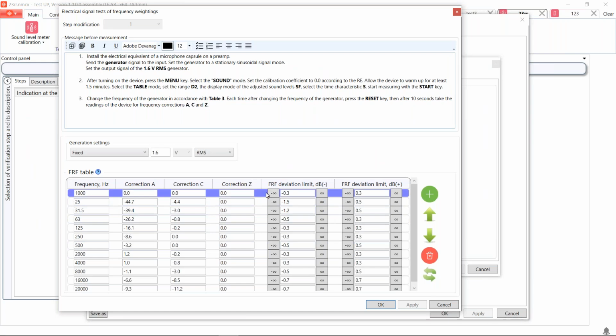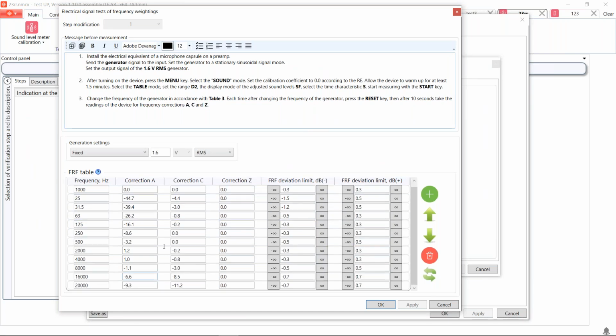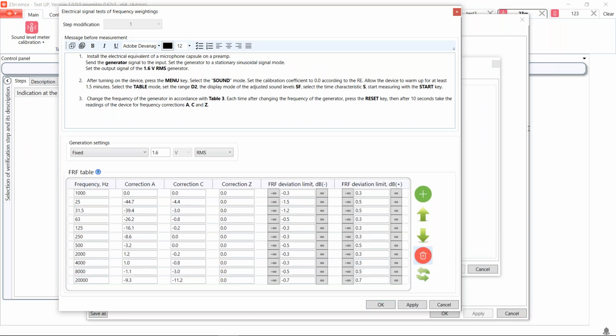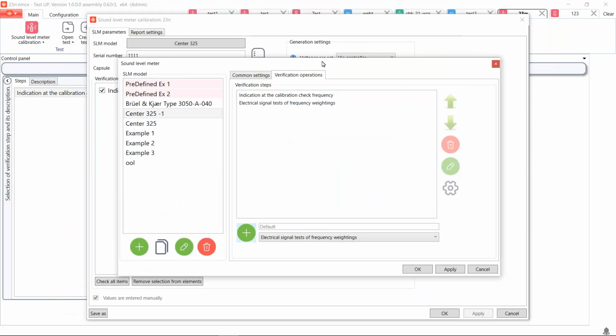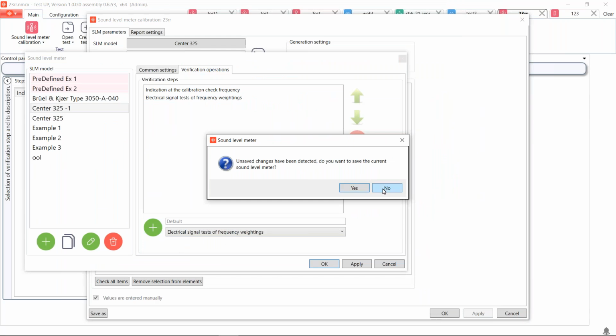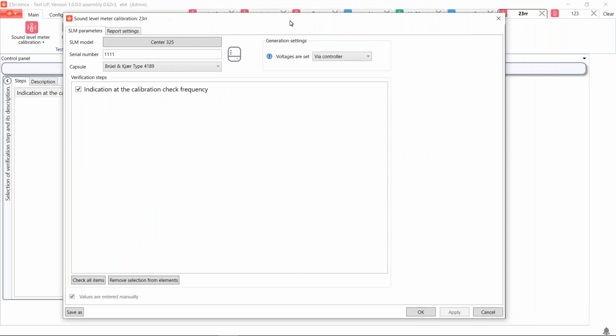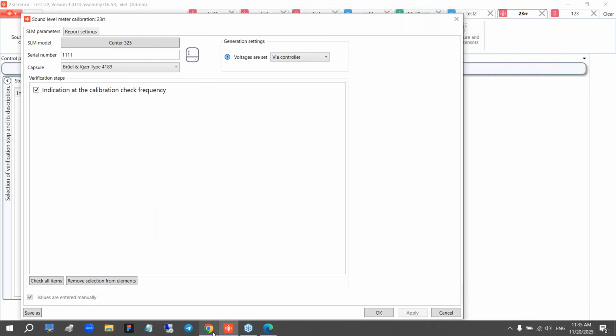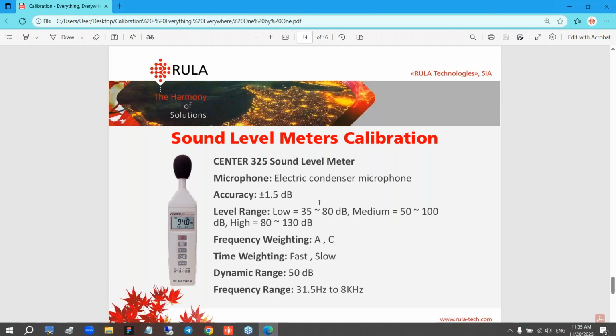Before performing the test, it is necessary to adapt the default measurement table by removing frequency ranges which are not supported by the sound level meter. This means that if you have a sound level meter with the frequency range from 1000 to 8000 hertz, for example, you don't need 16,000 hertz and 20,000 hertz, and you can just delete them this way. In the report settings, you can add the name of the calibration technician, environmental parameters, save the test, and at the end of the procedure, you will get the report. Okay, so this was a sneak peek into the sound level meter calibration, and we hope that this module will be soon released.